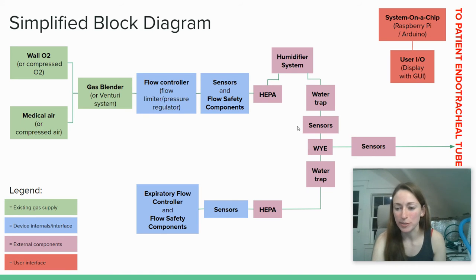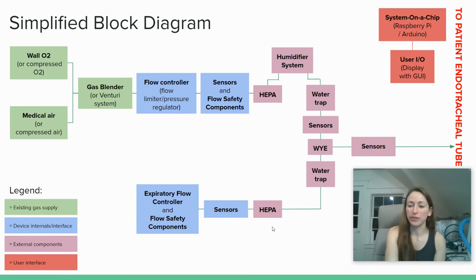Sensors, this sensor placement is optional. Sometimes the sensors are placed after the Y or within the device itself. And here's that Y that we mentioned. So from the Y, we can either move to the part of the circuit that goes to the patient, and there may be proximal sensors here, or we may move to the expiratory side. And again, there are water traps to prevent condensing liquid from moving through the rest of the system. There are HEPA filters to prevent contamination from the patient, as well as some expiratory sensors like flow sensors and pressure sensors, and the expiratory flow controller.